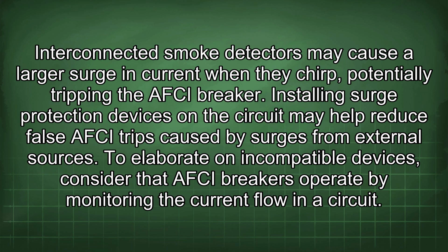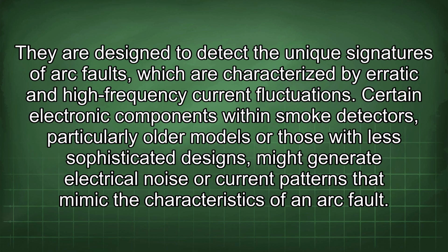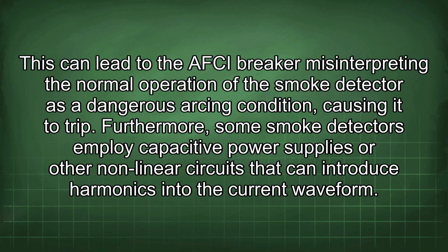To elaborate on incompatible devices, consider that AFCI breakers operate by monitoring the current flow in the circuit. They are designed to detect the unique signatures of arc faults, which are characterized by erratic and high-frequency current fluctuations. Certain electronic components within smoke detectors, particularly older models or those with less sophisticated designs, might generate electrical noise or current patterns that mimic the characteristics of an arc fault.